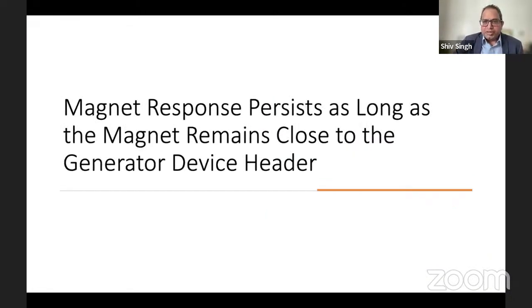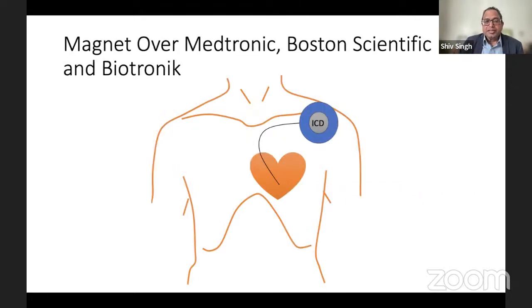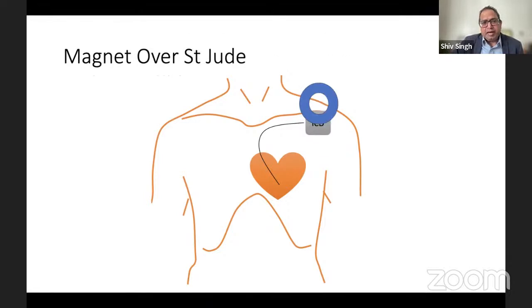The magnet response will persist as long as the magnet remains close to the generator unit. So if you want to use it for a long time, you need to tape it to the unit itself. And every pacemaker unit is different. If you've got a pacemaker from Medtronic, Boston Scientific or Biotronik, you can apply the magnet directly on the whole unit. But if the pacemaker is made by St. Jude, it needs to be applied on the header, that is the top end of the pacemaker. You don't apply it over it completely.